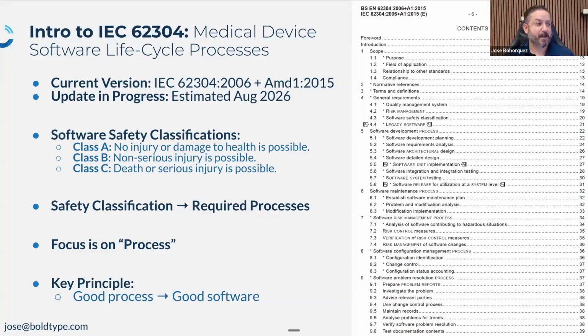Yeah. And one of the things expected in the next version is that there are also going to be just 2 classifications. But from what I've seen, it's not a match of basic and enhanced versus the 2 classifications that will be in the new version of 62304. It's almost like the mapping right now is pretty close. I think that's one of the upcoming slides. Class C is definitely enhanced, and then maybe 20% or 30% of products that are Class B would still be considered enhanced. That would be my estimate, Rob. I don't know if you've got a different one, but I think that's probably true.